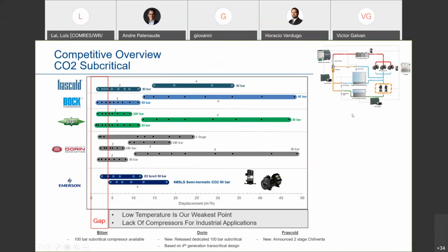So again, when we overlay our competitors, you can see here the application. We're talking about subcritical now. I mentioned we have two types of compressors. The scroll from a 21,000 nominal BTU, the ZO21, up to a ZO104. Those are the two ranges. And then on the 4MTL semi-hermetic line, we're down here in just under somewhere around the 34,000 BTU, 38,000 BTU, up here to, I think it's 85,000. I'll have to double check on the next slide.